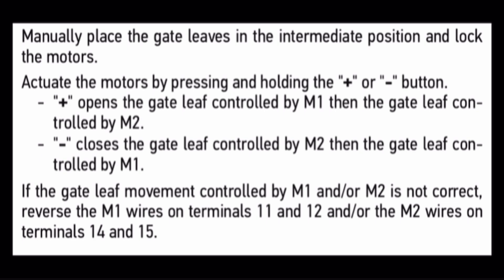Manually place the gate leaves in the intermediate position and lock the motors. Actuate the motors by pressing and holding the plus or minus button. Plus opens the gate leaf controlled by M1, then the gate leaf controlled by M2. Minus closes the gate leaf controlled by M2, then the gate leaf controlled by M1. If the gate leaf movement controlled by M1 and/or M2 is not correct, reverse the M1 wires on terminals 11 and 12 and/or the M2 wires on terminals 14 and 15.